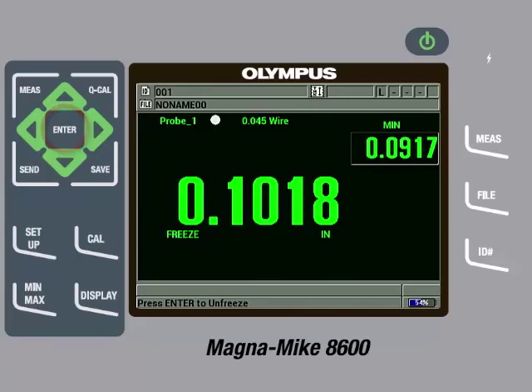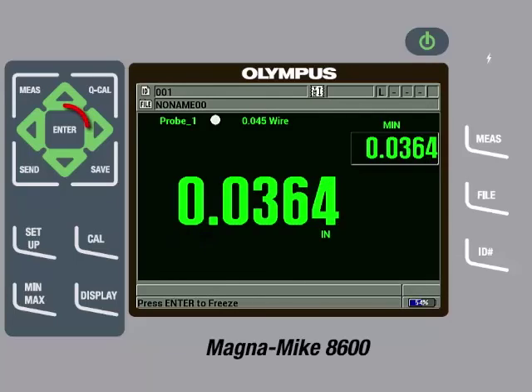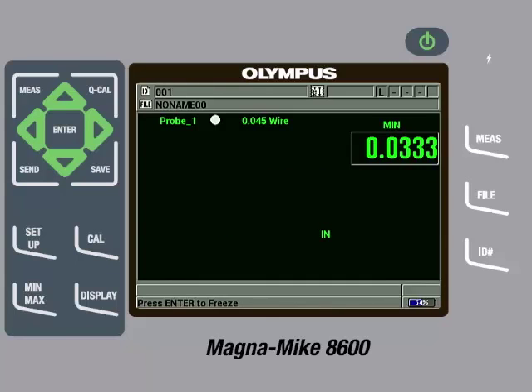We can press the Enter key to freeze the measurements on screen so we can rotate the part to measure the thinner side without capturing false readings. Once the thinner side is in contact with the probe tip, we can press the Enter key to unfreeze the measurements and the minimum thickness will be updated. These measurements can be saved to the internal data logger of the instrument, or they can be sent directly to a spreadsheet.